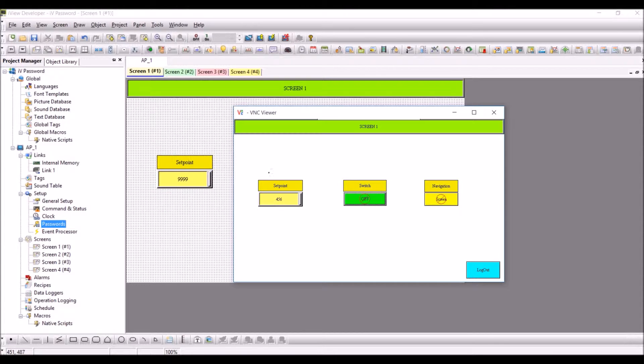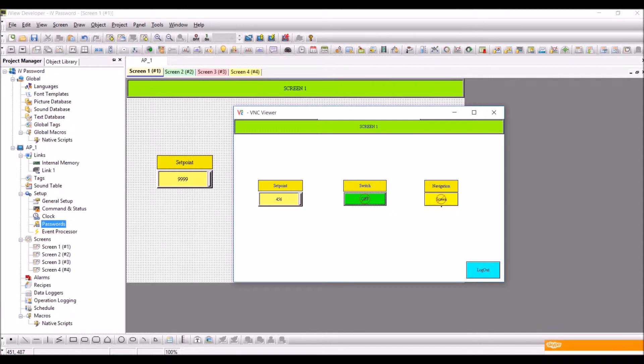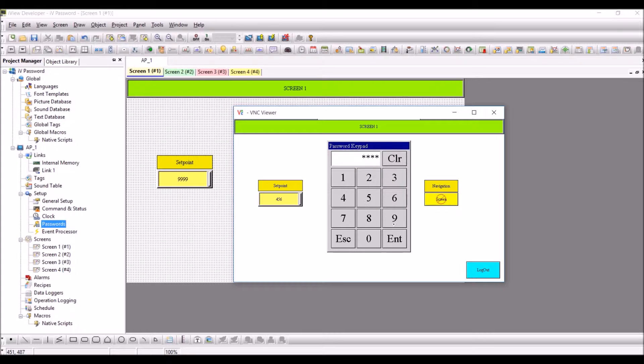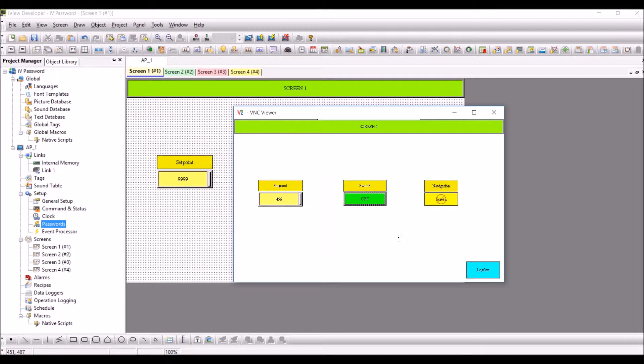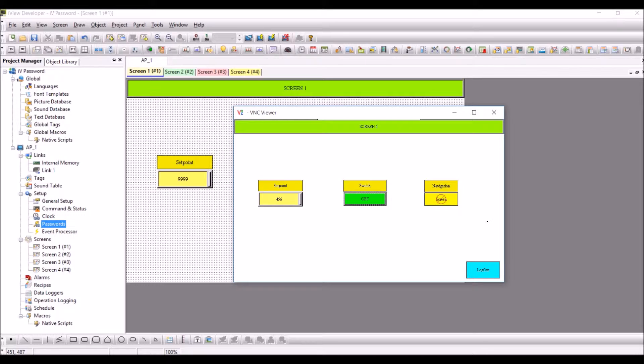This setpoint object has been configured for user level four, but the switch and the navigation have a higher value of user levels. Here you can see the switch is off. I am going to enter the correct password, one two three five, enter, and you can see the disable sign has been taken off. You can change the status of the switch to on or off.